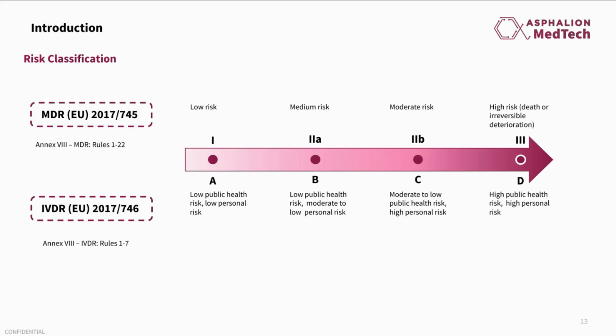Also, once you have identified that your technology actually maps to the definition of a medical device or an IVD in accordance with the European regulations, you need to assess the applicable risk classification for your product. Because depending on this risk classification, the number of requirements and also the conformity assessment procedure will be defined. Basically, for conducting this risk classification, you first need to know that devices are categorized into 4 risk classes: in the case of medical devices, ranging from class 1 to class 3, and in the case of IVDs, ranging from class A to class D. The principle for deciding the applicable risk classification is the application of several classification rules, 22 in the case of the MDR and 7 in the case of the IVDR. And basically, you need to choose the applicable risk classification depending primarily on the intended purpose of your device.